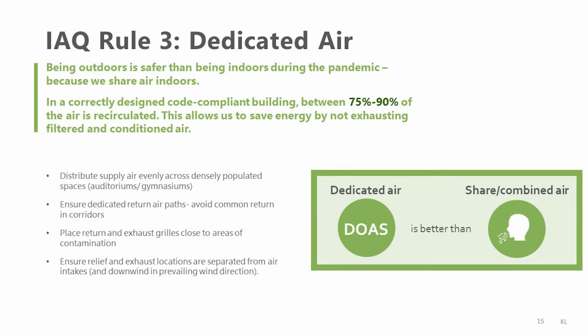So we think about how the air flows and where it comes in and where it goes out. But when the building is being renovated over the years, maybe that original intention wasn't really conveyed. And things were added in the wrong spot, maybe not a wrong spot, but not the most ideal spot. So maybe your outside air is not really spreading all over, but being short-circuited. Is your outside air really close to the return or the exhaust air? Are they placed in a strategic location so we can use the outside air that we brought into the building efficiently, and have it be breathed in by everybody, not just one area of people?